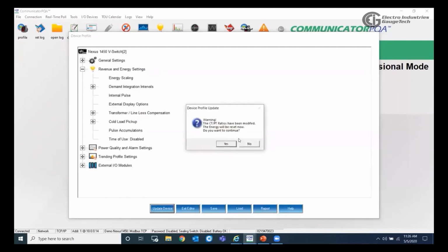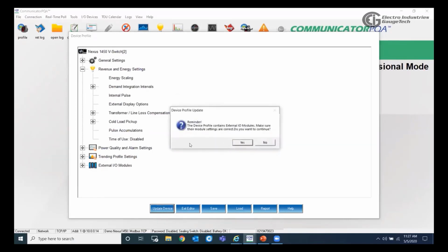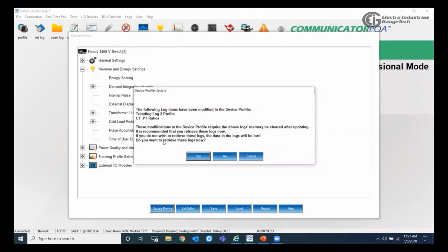And once we hit update device, because I did change the CT ratio, it's telling me that the energy will be reset, and I can hit yes if I want to continue. It's also asking if I want to continue to make sure the module settings are correct. It's okay. And when you do that, it will give you the option to retrieve the logs, because we changed the energy and CT settings, so the logs would be reset. Before resetting the logs, it gives you the option to retrieve them.